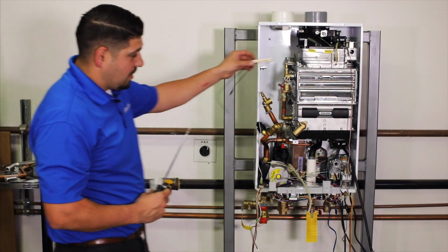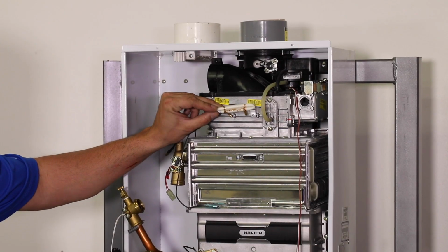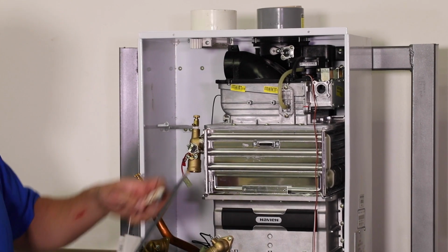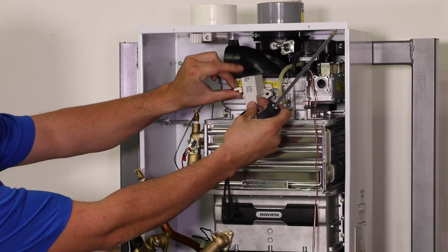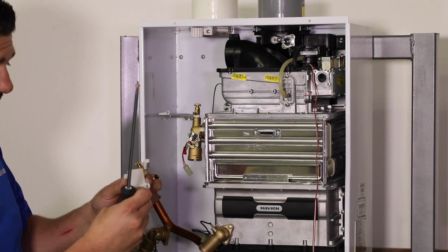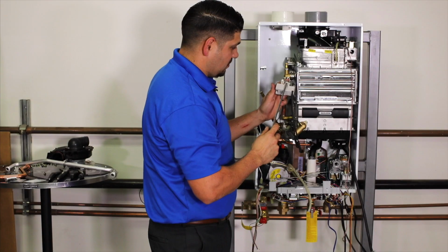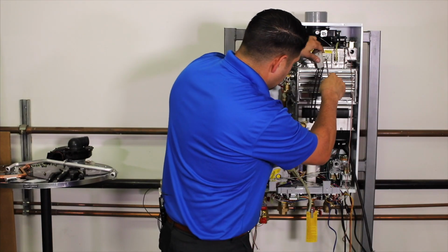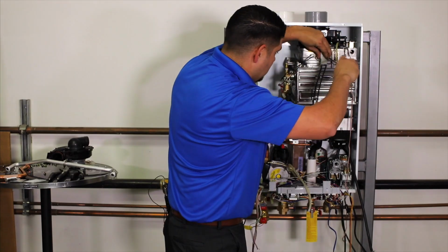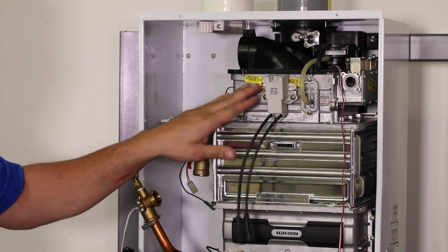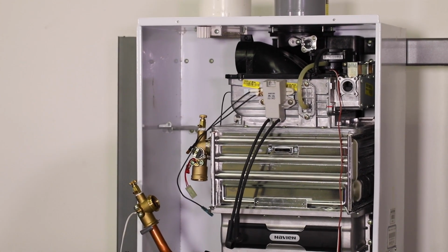When you're doing this, remember your thermal fuse bolts right behind your ignition transformer, like so. This goes here, and your ignition transformer right in front of that. Get that screw through both of them, kind of line that up. So thermal fuse and ignition transformer are back installed.